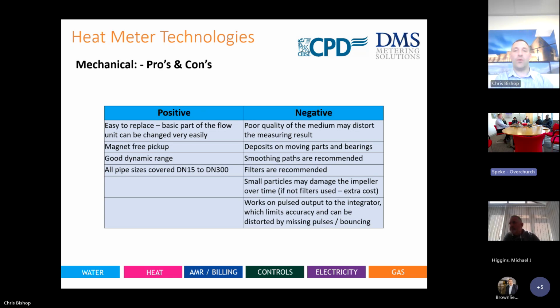The negatives are all down to water quality and how they need to be installed. Water quality: if you have a heating system that's not maintained over time, you get crud inside, your inhibitor is low. Heating systems generally eat themselves inside if they're not maintained correctly. Naturally, they're going to eat the devices inside the heating system, so anything that's a moving part with bearings will die and corrode over time. That causes inaccurate readings. So the meter slows down, sticks, stops, and that's where the data is obviously lost as well.